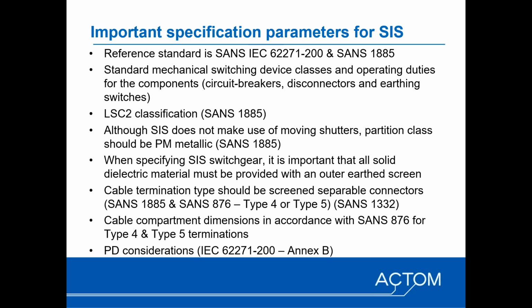And then lastly, some thoughts. Johan has shown us videos and described in detail the partial discharge phenomena. By virtue of the earth screen layer, the concern over surface discharge, in other words the dry band arcing associated with leakage currents along the surface of an insulator, is eliminated, as well as corona, because there's no exposed insulation. There is the possibility of voids within the solid dielectric, and that comes down to the quality of the manufacturing and the routine testing of the switchgear.